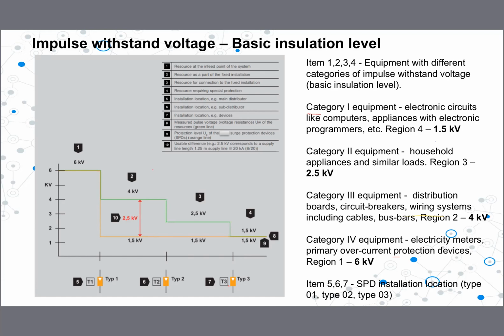Category 1 equipment are the equipment you can find down the line of the electrical system, right? Electronic circuits, computers, those kinds of things. In this graph, this region, right? The insulation level, the maximum voltage that this equipment can handle, is 1.5 kilovolts, very low. Then category 2, household appliances and other stuff, which is further up the system compared to region 4.